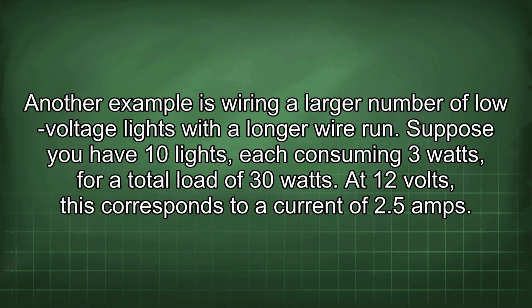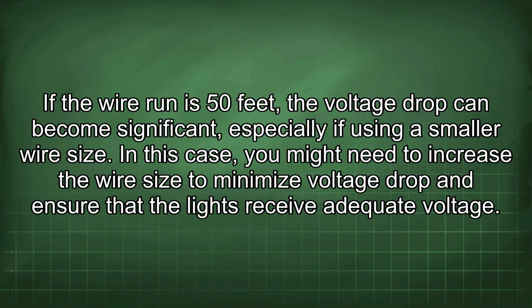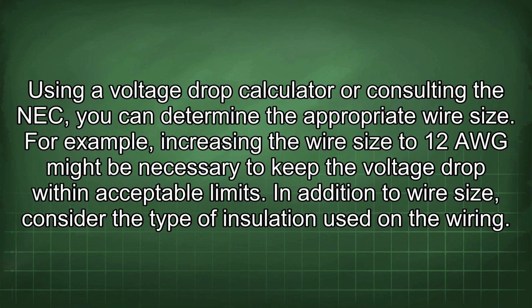Another example is wiring a larger number of low-voltage lights with a longer wire run. Suppose you have 10 lights, each consuming 3 watts, for a total load of 30 watts. At 12 volts, this corresponds to a current of 2.5 amps. If the wire run is 50 feet, the voltage drop can become significant, especially if using a smaller wire size. In this case, you might need to increase the wire size to minimize voltage drop and ensure that the lights receive adequate voltage. Using a voltage drop calculator or consulting the NEC, you can determine the appropriate wire size. For example, increasing the wire size to 12 AWG might be necessary to keep the voltage drop within acceptable limits.